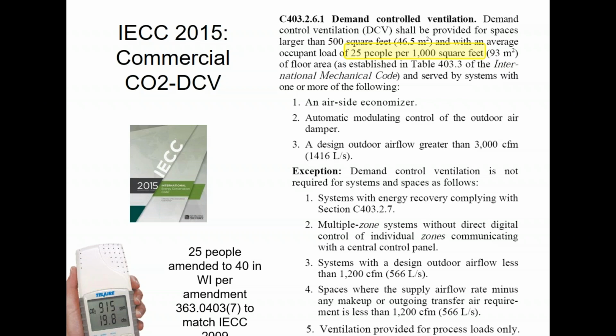There are a few exceptions to that. If you have small systems, you don't have to do it. If you have a zone dampered system with pneumatic controls, that would be exception number 2 there, and you would not have to do it. But if you have a constant volume system or you have DDC VAV, then you would be in the category of having to do demand ventilation on these high density type spaces. Typically, it's conference rooms, meeting rooms, movie theaters, things like that, where we have a lot of people in a relatively small space.